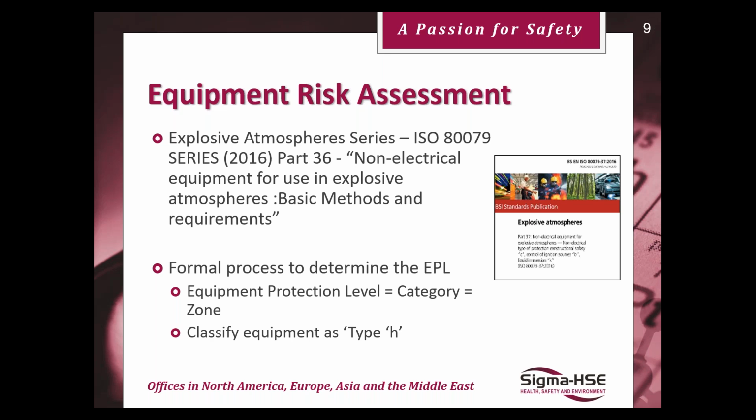And the other category is category 3, which is the least risky. It's less risky because it appears for a shorter amount of time, so it's more like abnormal conditions. For example, something leaks, or there's an abnormal event like a spill or a rip. In a dust collector, your filters can rip and that can lead to a carryover of powders. So it's an abnormal condition. It doesn't appear frequently. So this is the process.